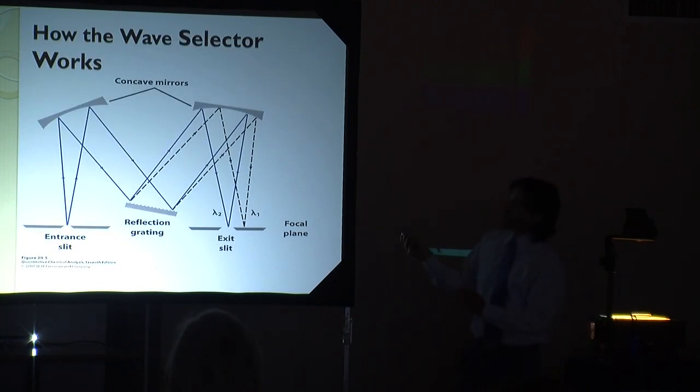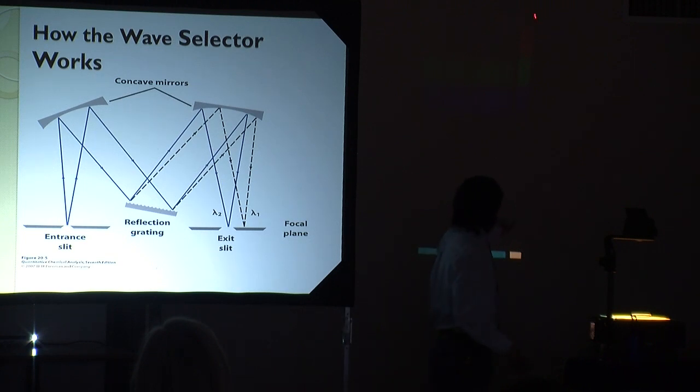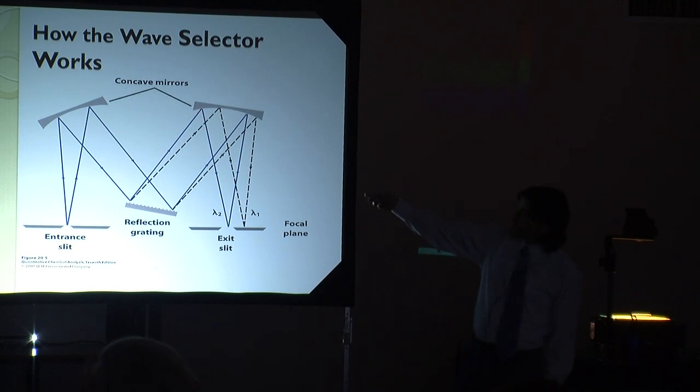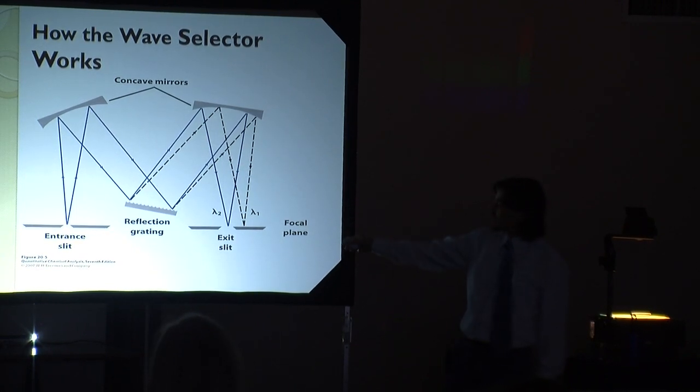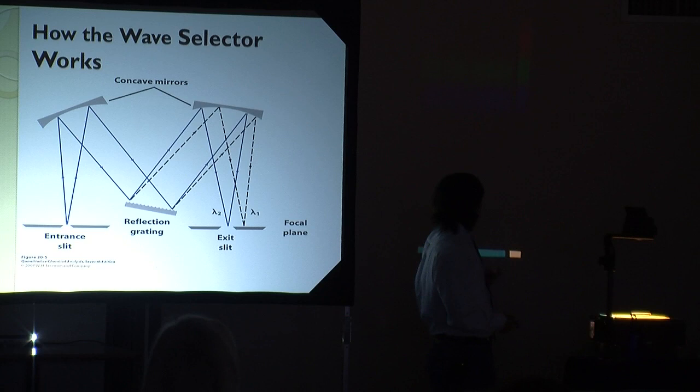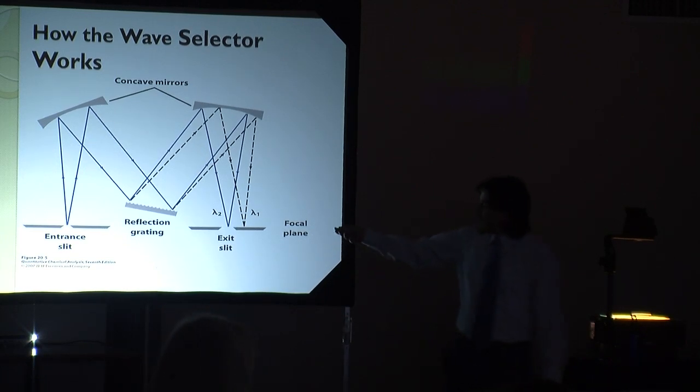This is how our instruments work. The wave selector has a light source here, which is white light. It enters in through the slit and bounces off of a mirror. That mirror reflects the light onto a grating here, and that grating spreads the light out into a rainbow, essentially like this. The rainbow has various points of impact for each wavelength. By moving this grating back and forth, we can select an individual wavelength - say blue, green, red, any color that we want - and that is the only color that will come out of this slit. All the other colors are absorbed by the walls of the instrument.